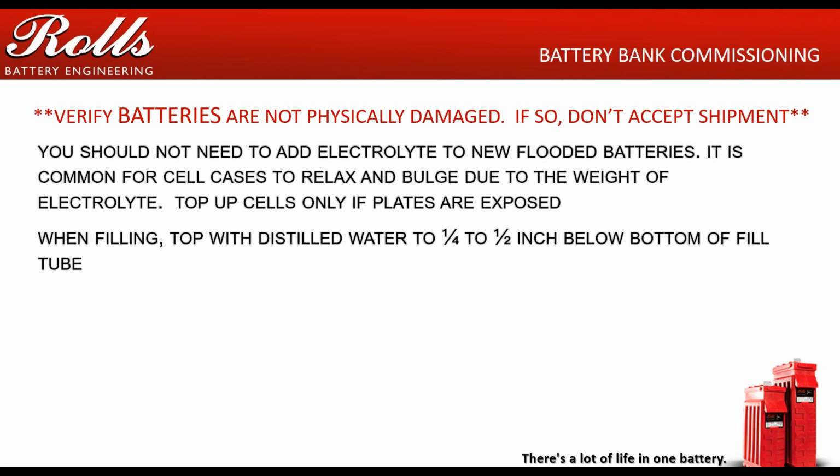If you go closer to the bottom of that, as the battery is charging, or if you're doing an equalization charge, the electrolyte has the possibility of overflowing out of the battery, and that's not a good thing either. When you're using deionized water or reverse osmosis water, try to get your pH as neutral as possible.